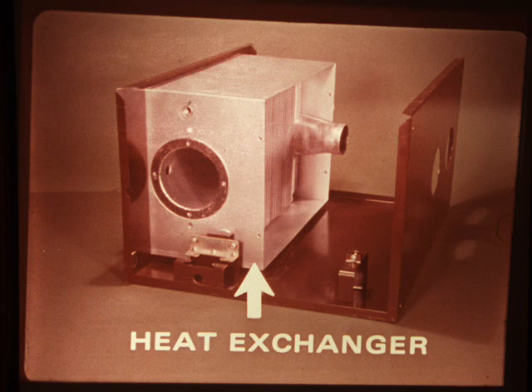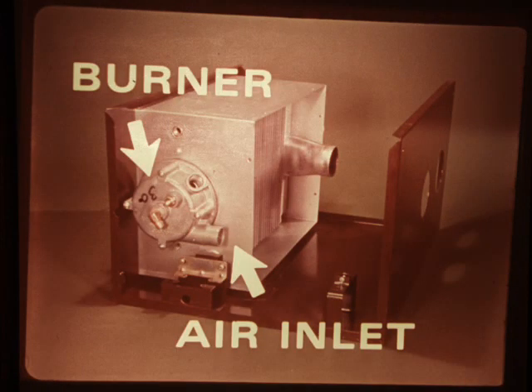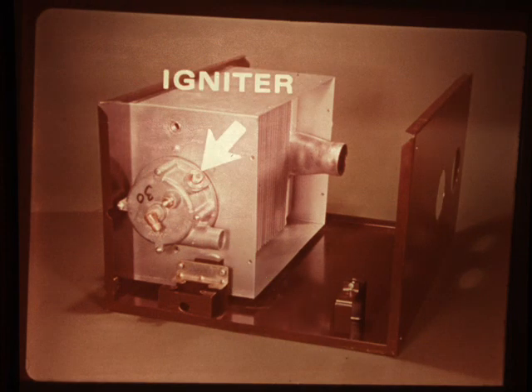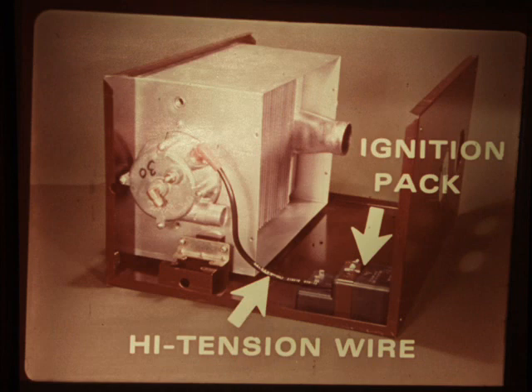The main components of the furnace are the heat exchanger, which is heated directly from the flame rather than by heated air, and the burner, which mounts on the end of the heat exchanger and has a forced air inlet fitting for combustion air. The igniter fits into the burner, and it operates very much like a spark plug. However, it fires continually. High voltage spark is supplied from the ignition pack, a sealed unit which does the same job as the coil and distributor on a gasoline engine, but with only one high-tension wire to the igniter.